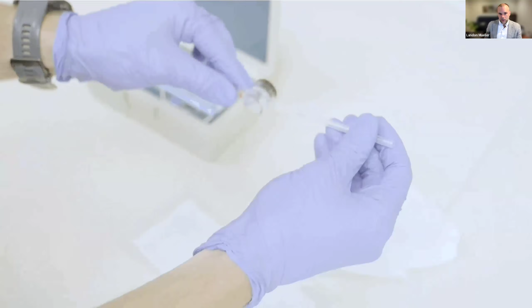And then you're going to fill the chamber stem. What this does, when you fill everything with saline, is create a continuous column of fluid. You basically want fluid extending all the way from the muscle where the patient's at, all the way through the needle, back through that chamber pressure, so that the device can measure that pressure. So when everything is continuous, you're measuring the pressure even though the device is outside of the skin. There's that continuous pressure column. So that's how we actually measure the pressure without leaving the device in there.